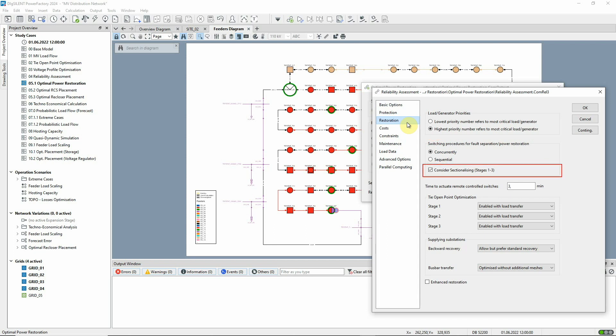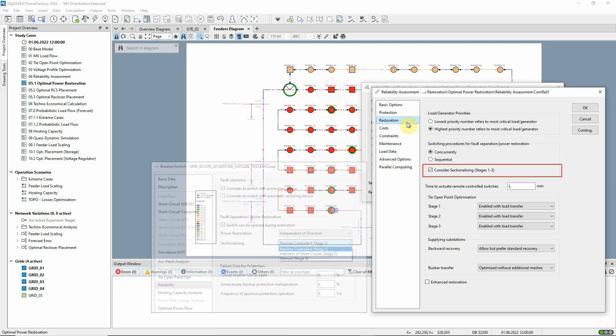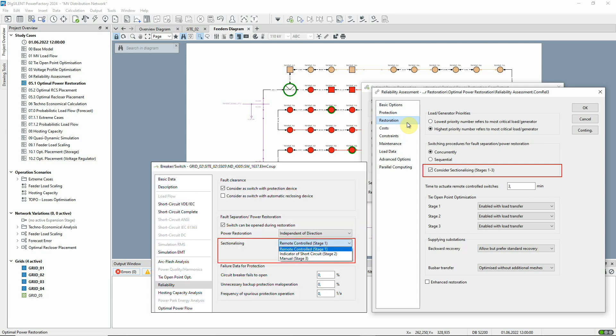Here we've opted to consider sectionalising, which influences how quickly switches can be operated. To understand this option, let's look at a typical circuit breaker. If stage 1 is selected, the switch can be operated remotely. If stage 2 is selected, the switch must be operated locally, but its status is available outside the switch enclosure. Stage 3 switches have to be visually inspected to determine their status before being operated, so this takes the longest.